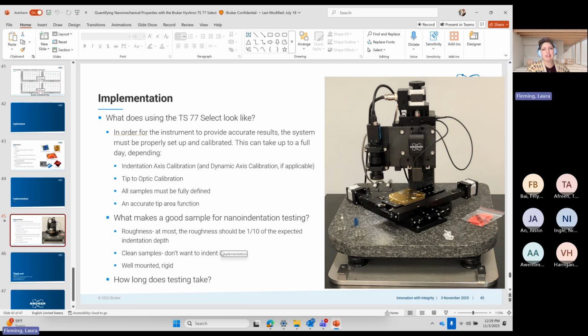You need clean samples, and they need to be rigidly mounted. This is something that I think is often missed in training: how to mount a sample well. Your system has screw-in sample mounts available should we need them, but typically we find that the magnet is sufficient. There are magnets in the stage, and our typical recommendation is to glue the sample to an AFM puck and test it that way. People often want to skirt this, but you have to use super glue. People try to use things like whiteout or double-sided tape. They're too compliant and too drifty. You're not going to be able to get accurate results.